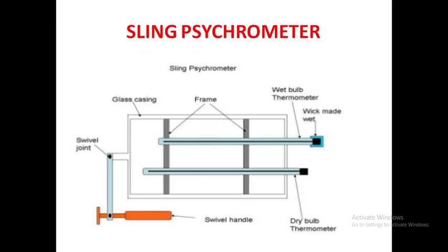If the wick is covered with dirt, the wick will become stiff and its water absorbing capacity will reduce. However, a stiff or dirty wick will resume normal function when boiled in hot water.